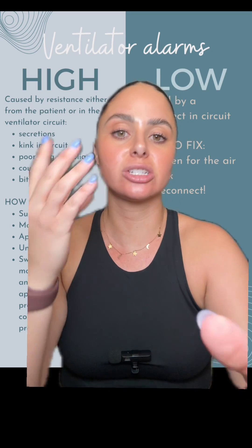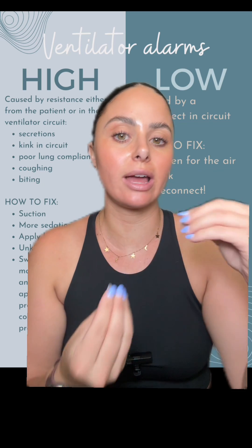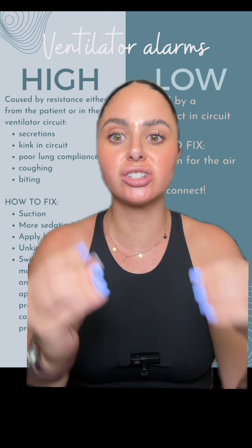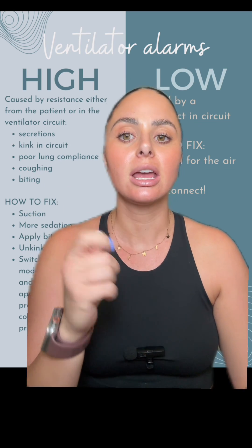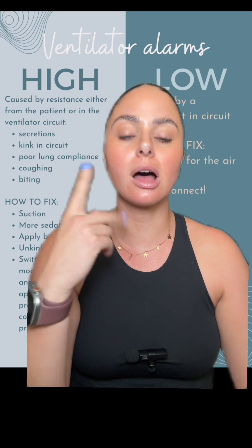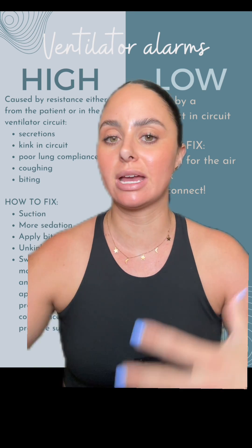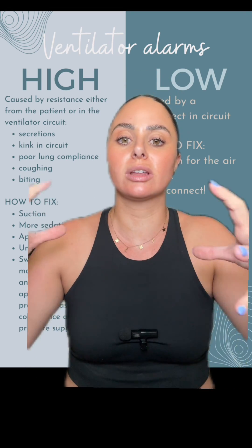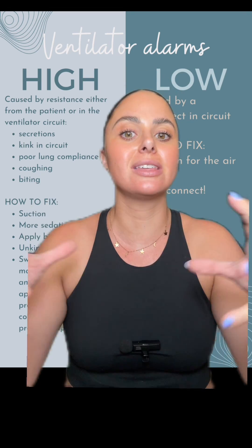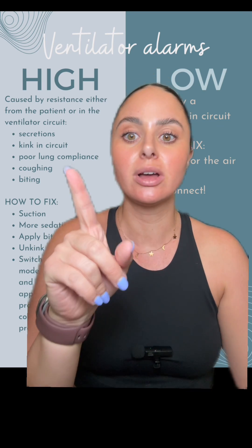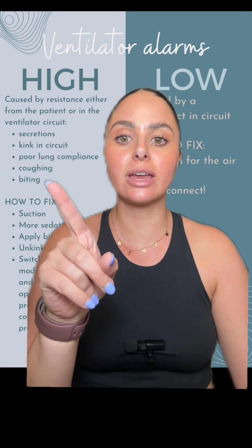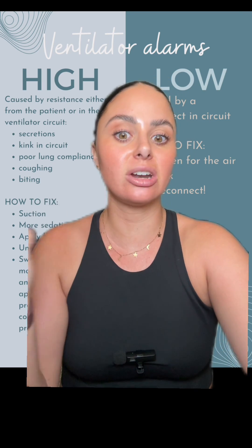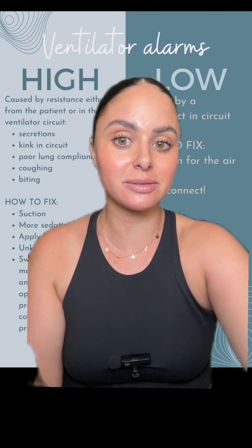The main causes are things like secretions — if you have a bunch of secretions in there — a kink in your circuit, poor lung compliance, meaning the patient may have smoked for a long time and their lungs don't stretch the same way. Coughing and biting can also cause high pressure alarms.